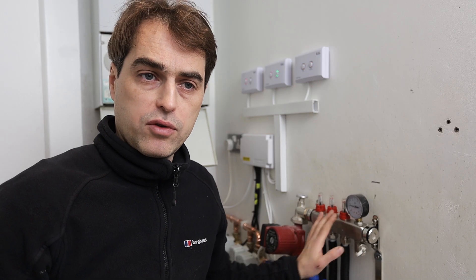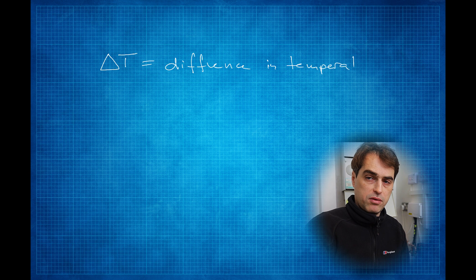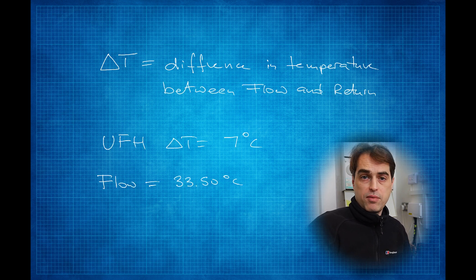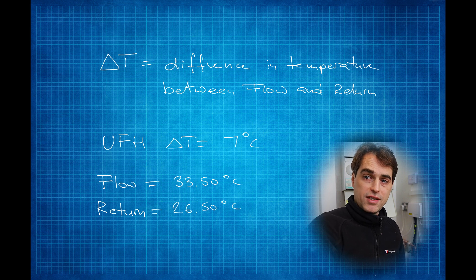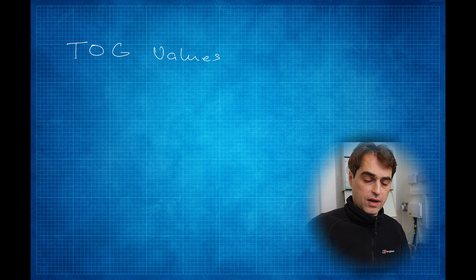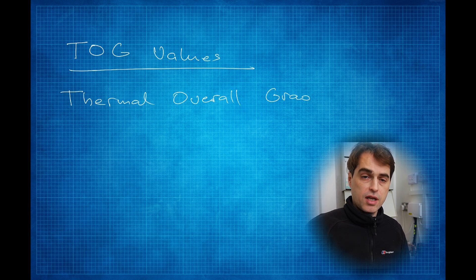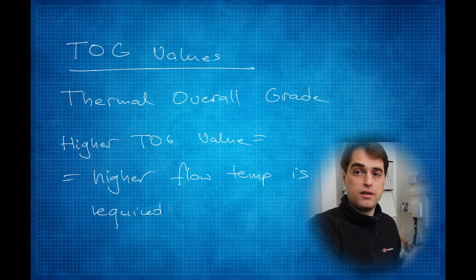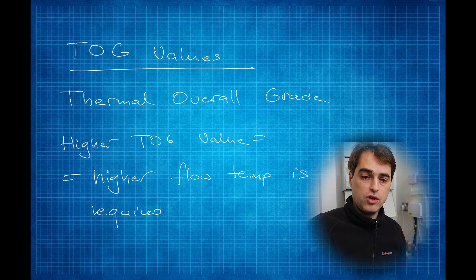If we run the manifold at a delta T — the difference between flow and return — of 7 degrees, then the flow needs to be 33.5 degrees and the return 26.5 degrees. We also have TOG values, which represent the insulating properties of floor coverings. The higher the TOG value, the higher the flow temperature has to be to overcome the resistance of the floor covering, so keep that in mind.